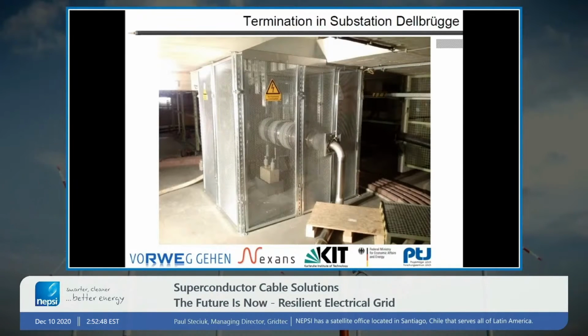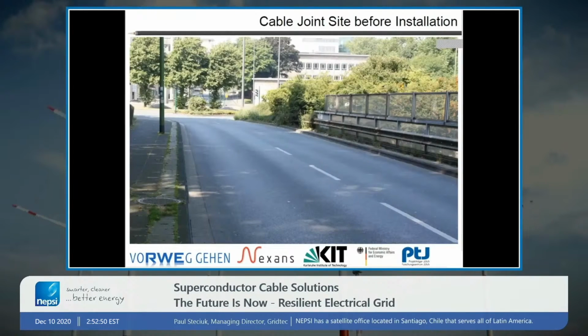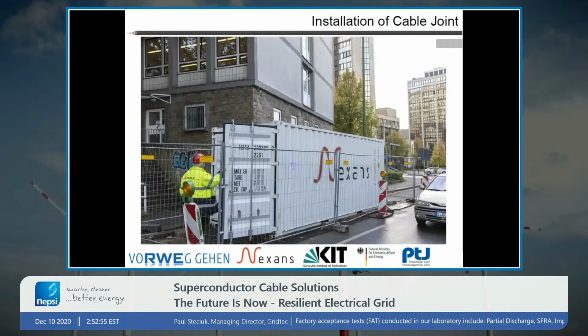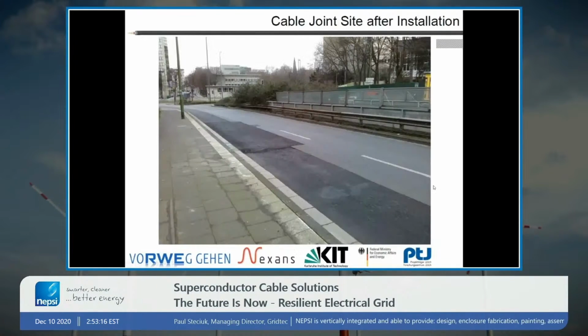Here's where the splice for the cable would be installed. So the splice does require specialized labor. The manufacturer of the cable, in this case Nexans, also provides the labor to do the splice. And what they do is they have this shipping container that has no bottom, and they put that over the place where you're going to do the splice, and then they do the work so they're outside of the elements. And then they just go ahead and pave right over the splice box.